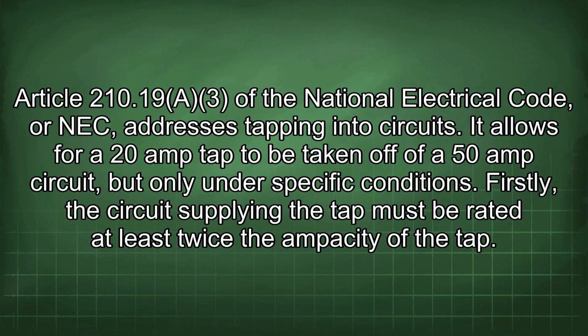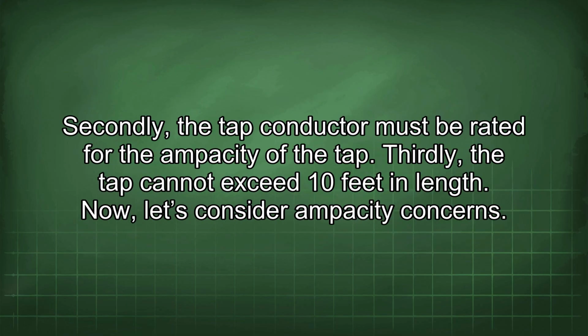Article 210.19(A)(3) of the National Electrical Code, or NEC, addresses tapping into circuits. It allows for a 20 amp tap to be taken off of a 50 amp circuit, but only under specific conditions. Firstly, the circuit supplying the tap must be rated at least twice the ampacity of the tap. Secondly, the tap conductor must be rated for the ampacity of the tap. Thirdly, the tap cannot exceed 10 feet in length.